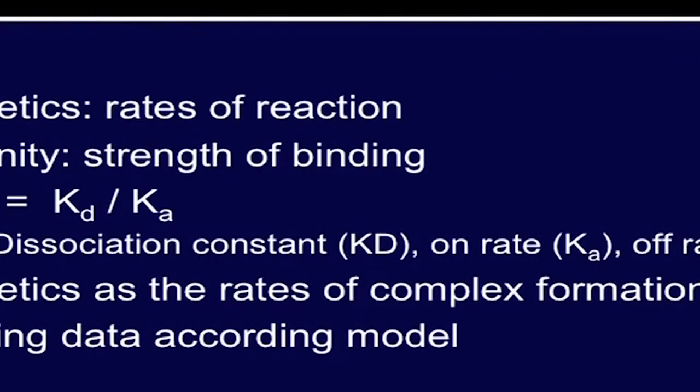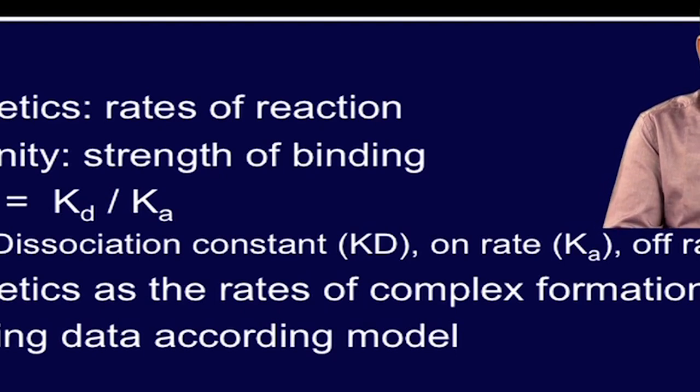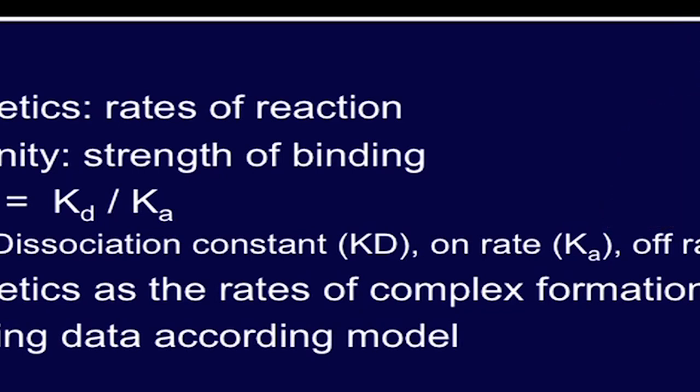By using SPR imaging, the kinetics and affinity can be determined. Kinetics represents the rate of reaction, whereas affinity shows the strength of binding. KD or dissociation constant is represented by kd divided by ka, where kd is the off-rate and ka is the on-rate. Therefore, kinetics, which represents the rate of biomolecular complex formation, can be evaluated by processing the raw data and further fitting the same into the appropriate models.